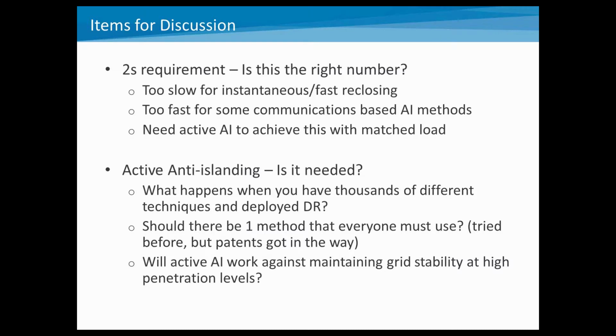The other thing about 2 seconds is it may actually be too fast for some communication-based methods. So some of the phasor-based methods or other communication-based methods may require more than 2 seconds to determine if an island is occurring. And the third point there is the need for active anti-islanding to achieve this number. So 2 seconds is probably only going to be achieved with active anti-islanding. And so these are things just to think about.